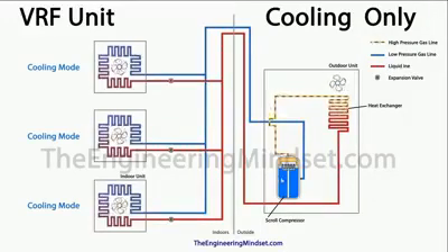So the refrigerant is leaving the compressor as a high pressure, high temperature superheated vapor. And there's a fan in the outdoor unit which is sucking air in and then going across the heat exchanger, and the hot air is then exhausted and rejected out of the top of the unit. And as the air comes across the heat exchanger, then that heat transfer occurs. So this refrigerant inside the condenser here starts to cool down and condense into a liquid. So by the time it leaves the heat exchanger, this will now be a high pressure, medium temperature saturated liquid. And this refrigerant now flows continuously around the building, around this common pipework, and all of these units will feed off of this.